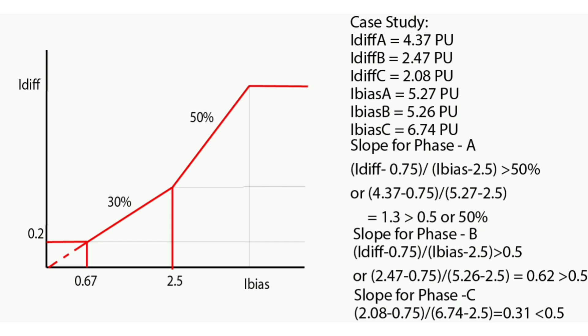For phase B, using the same formula — (I_differential minus 0.75) divided by (I_bias minus 2.5) — which must be greater than 0.5: the differential current is 2.47 per unit and bias current is 5.26 per unit. So the slope equals (2.47 minus 0.75) divided by (5.26 minus 2.5), which equals 0.62 — greater than 0.5 or 50%. Again, for phase B, the differential current remains in the tripping region.